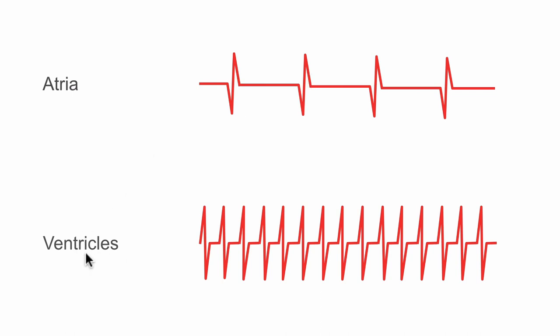But here, interestingly, on the ventricular lead, we're picking up multiple depolarizations, some very fast activity coming from the ventricle itself. So we're getting two bits of information to help us ascertain what that rhythm is. Now because there's more ventricular events than atrial events, we can be really confident in saying that this is a ventricular arrhythmia.